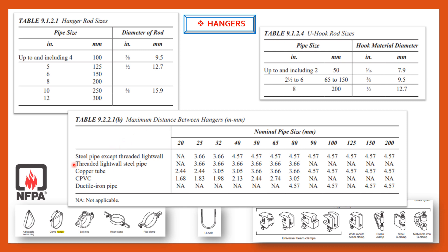Generally, we use steel pipes. For steel pipes, if you are using 1-inch pipe, that is 25 mm pipe, then the distance between hanger to hanger can be 3.66 meters. And if we have 100 mm pipe, then the distance between hangers can be 4.57 meters as per NFPA 13. And from table 9.1.2.4, we can identify the hook material diameter based on the pipe sizes.